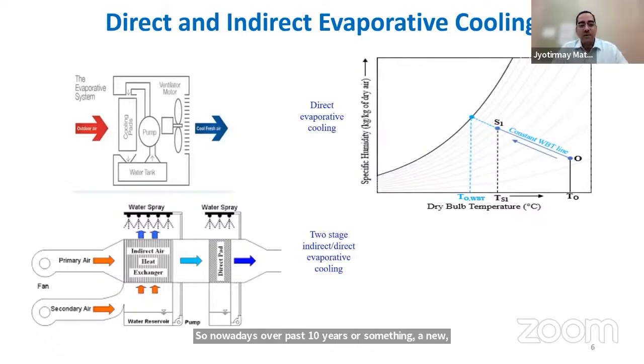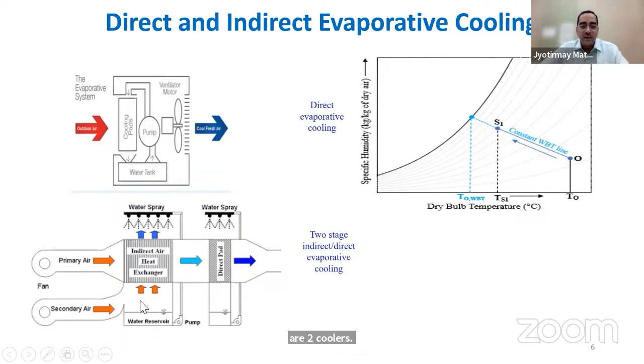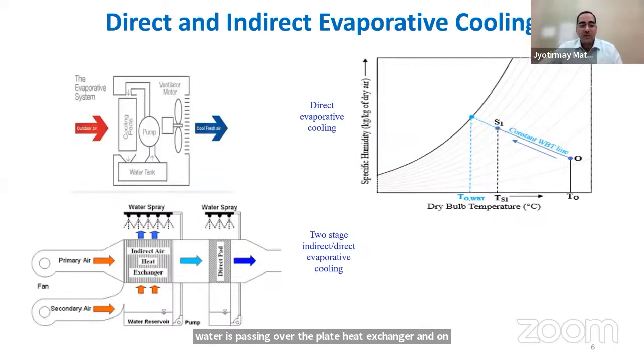Now we have two air streams, the primary air and the secondary air. You can say these are two coolers side by side, one after the other. One cooler is just cooling the water, and that water is passing over a plate heat exchanger. On the other side of the plate, my air is flowing. So the air from the first section, the orange one, to the blue one, is not getting any additional moisture. It is just getting cooled, which is called sensible cooling. Then, whatever remaining cooling effect is to be obtained, you can have a water-based evaporative cooler, a regular cooler, and then you can get it.